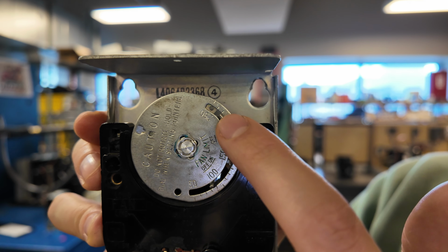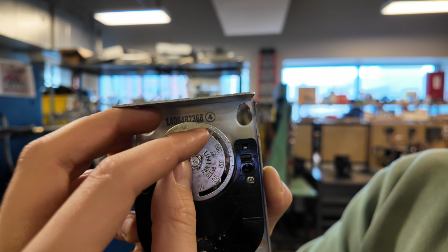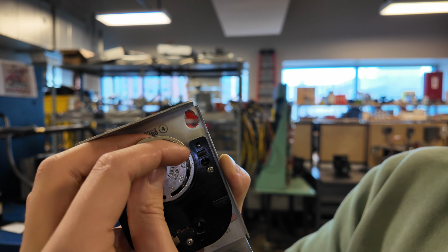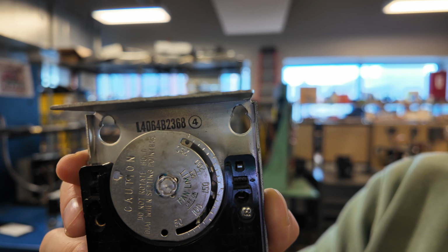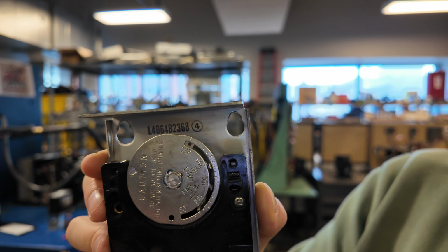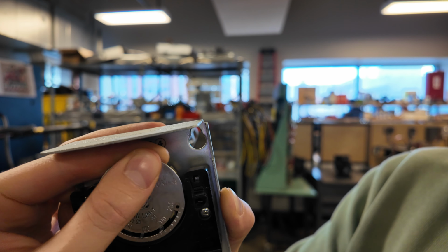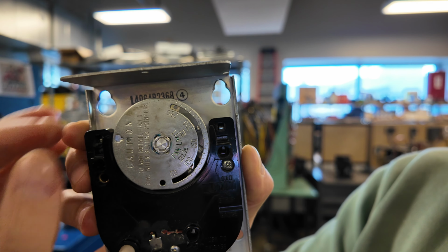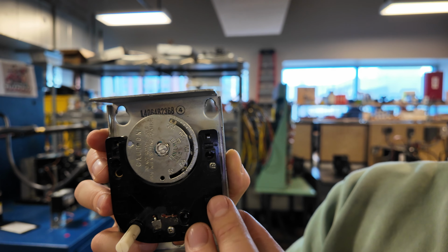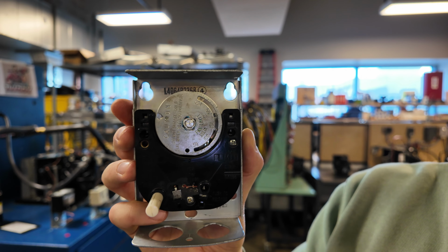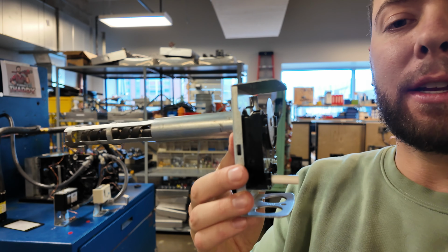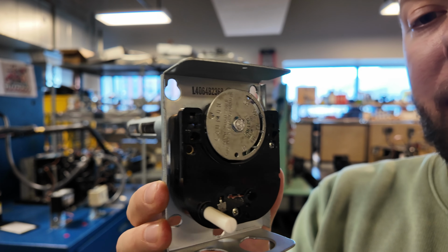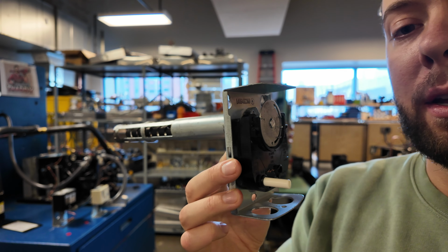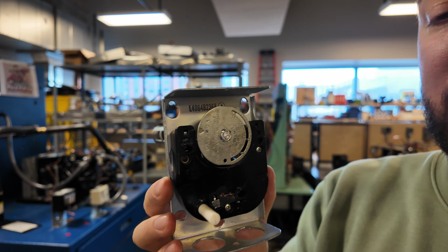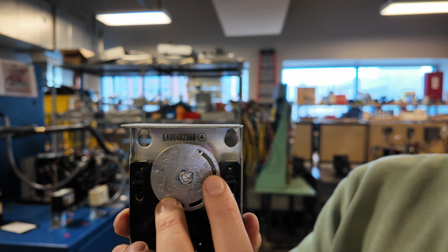That third arm is actually for the high limit. In our area, most people like to set the high limits around 180. Oh, this one's a little stiff. But people like to set the high limits around 180, so right there. If this dial was to spin and hit that, hear that click? Hit that 180 set point, it's actually going to open the contacts and turn power off to the gas valve as a safety. So once again, a fan control controls the blower, and it also controls voltage flowing to the gas valve. It acts as a high limit. So you need to set the cutout first, cut in, and then high limit.